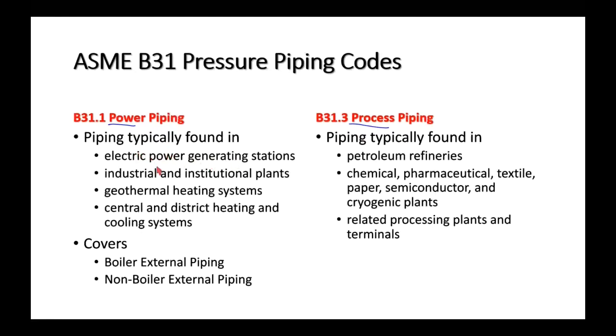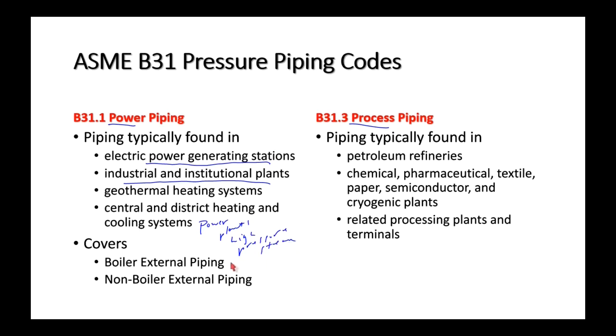The power piping code covers what you find in power generation stations and industrial or institutional plants — basically power plants that generate high-pressure steam. This covers boiler external piping and non-boiler external piping. The process piping code covers petroleum refineries, chemical, pharmaceutical, textile, pulp and paper, semiconductor, and cryogenic plants — basically processing plants.